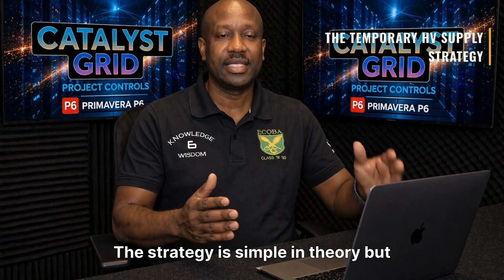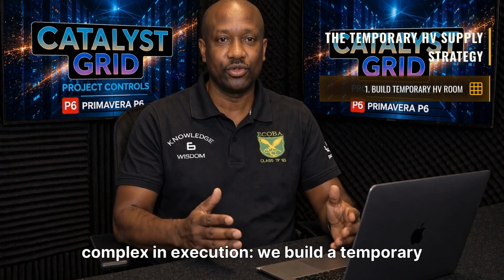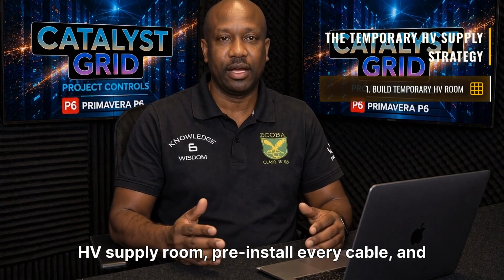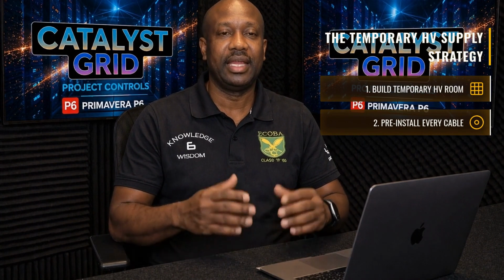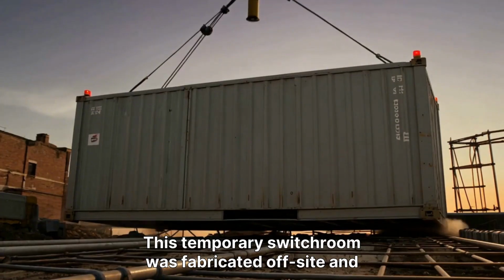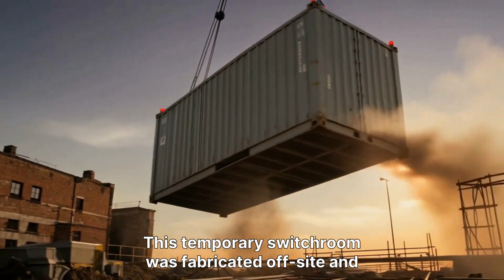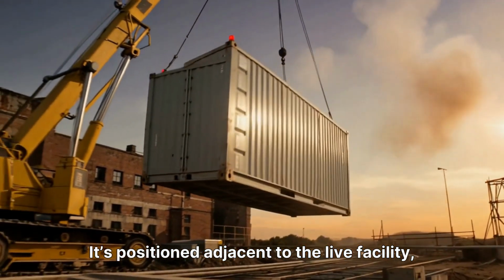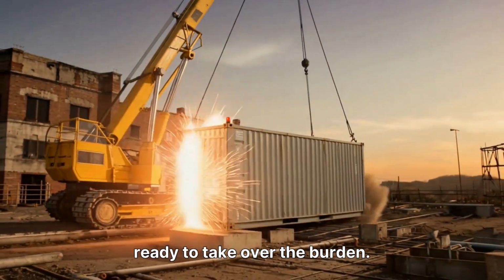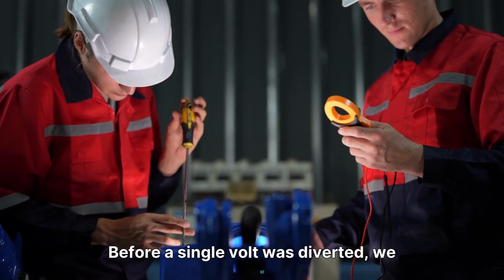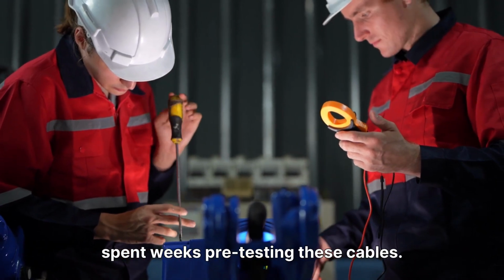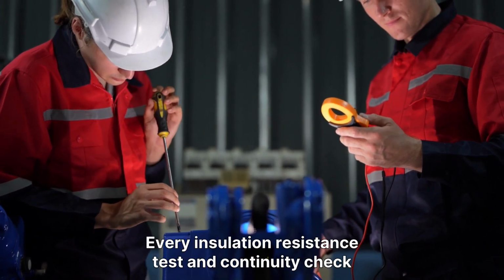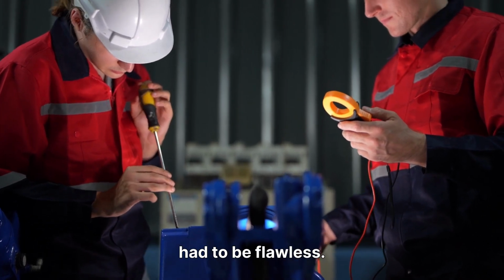The strategy is simple in theory, but complex in execution. We build a temporary HV supply room, pre-install every cable, and then cut over feeder by feeder. This temporary switch room was fabricated off-site and brought in. It's positioned adjacent to the live facility, ready to take over the burden. Before a single volt was diverted, we spent weeks pre-testing these cables. Every insulation resistance test and continuity check had to be flawless.